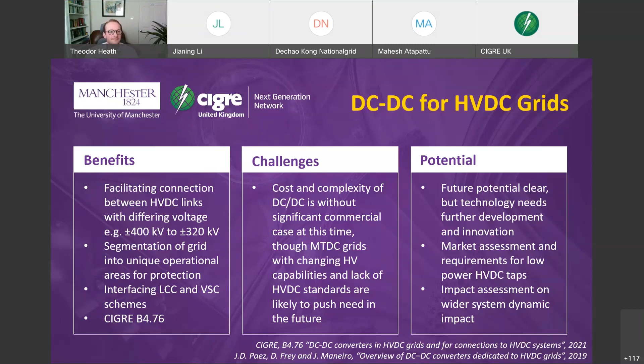One of the big considerations at the moment is assessing the impact of high levels of non-synchronous generation, for example systems that are grid following, as Dechao has already explained, or grid forming. The Migrate project has concluded there is a maximum limit of about 68% of connection generation by means of grid following converters, and the rest needs to be made up of traditional synchronous generation or converter interface generation using grid forming control.